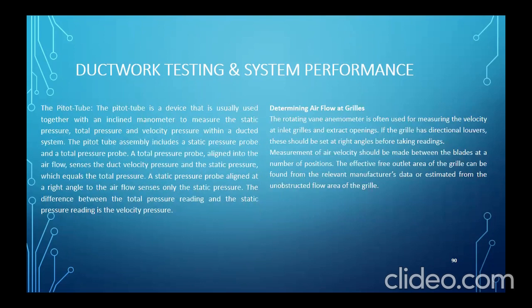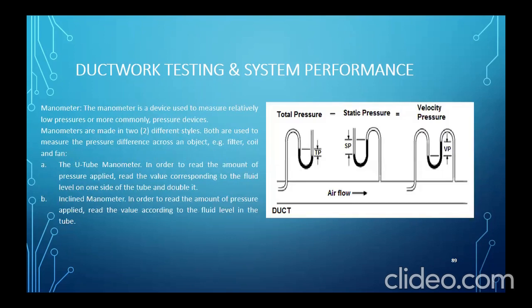Basta, a pitot tube is a device that is usually used together with an inclined manometer to measure the static pressure, total pressure, and velocity pressure within a duct system. So this is the pitot tube.